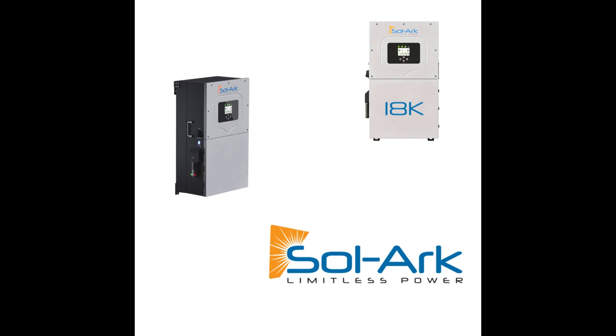We also have a very high surge current. I don't think that any products can really compete with our off-grid surge current for those larger loads like an HVAC system or some sort of large pumps, like a well pump, off-grid. We have a 36 kilowatt 10-second surge for those high LRAs, or locked rotor amperage requirements, off-grid. It is a standard 120/240 volt connection for your split phase connections. It can operate in 208 3-phase, but typically once you're operating at that size, we recommend our commercial products like the Sol-Ark 30K. And then it is a stackable system, up to 12 in parallel.